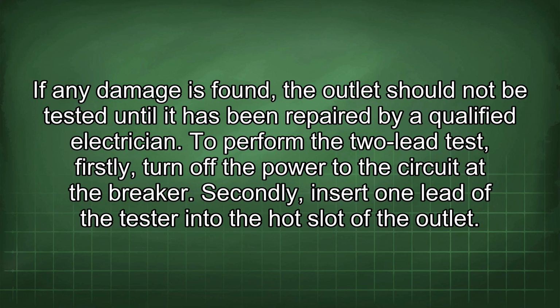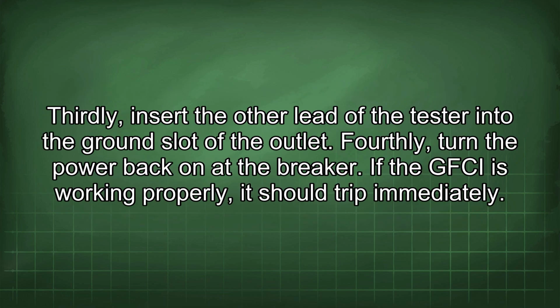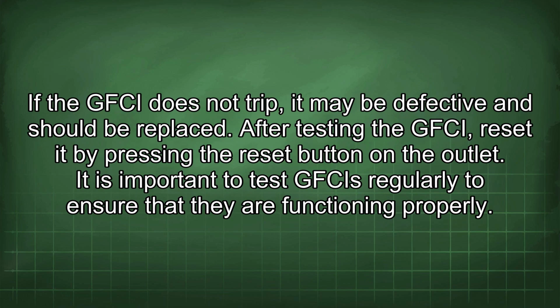To perform the 2-lead test, firstly turn off the power to the circuit at the breaker. Secondly, insert one lead of the tester into the hot slot of the outlet. Thirdly, insert the other lead of the tester into the ground slot of the outlet. Fourthly, turn the power back on at the breaker. If the GFCI is working properly, it should trip immediately. If the GFCI does not trip, it may be defective and should be replaced. After testing the GFCI, reset it by pressing the reset button on the outlet.